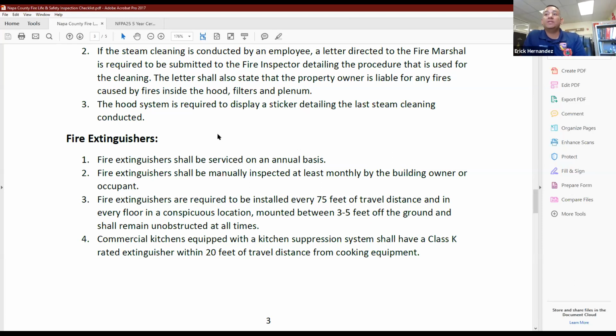A couple of things with fire extinguishers: in a commercial setting, typically, and not always, but typically, you're required to have a minimum rating of 2A10 BC fire extinguisher within 75 feet of travel distance from anywhere in the interior of the property. And these fire extinguishers have to be properly mounted between 3 and 5 feet off the ground and shall be kept unobstructed. So again, no furniture or Christmas trees. For some reason, I find a lot of Christmas trees during the winter months blocking the fire extinguisher. So try to keep 3 feet away from any obstructions, and make sure you have the proper signage and they can be identified.